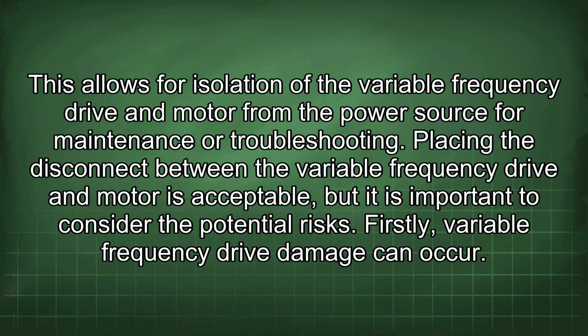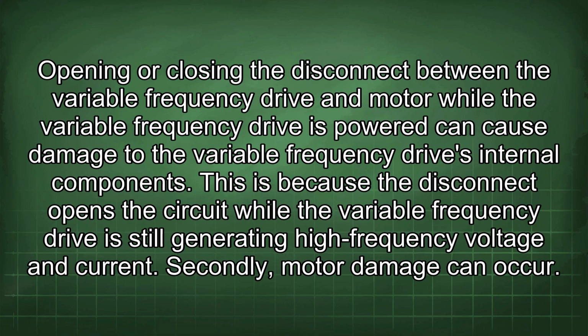Placing the disconnect between the variable frequency drive and motor is acceptable, but it is important to consider the potential risks. Firstly, variable frequency drive damage can occur. Opening or closing the disconnect between the variable frequency drive and motor while the variable frequency drive is powered can cause damage to the variable frequency drive's internal components. This is because the disconnect opens the circuit while the variable frequency drive is still generating high frequency voltage and current. Secondly, motor damage can occur.